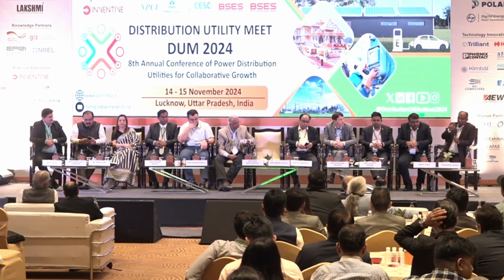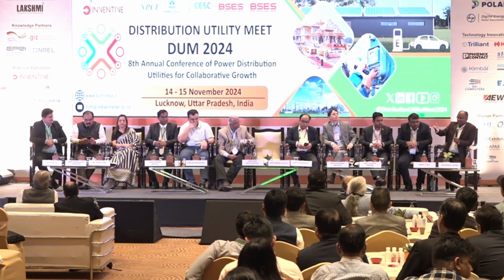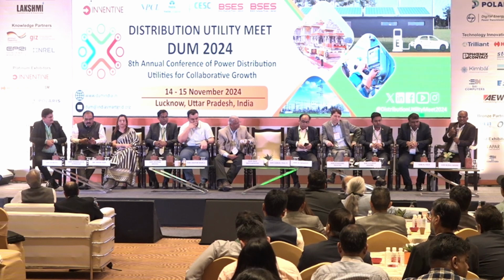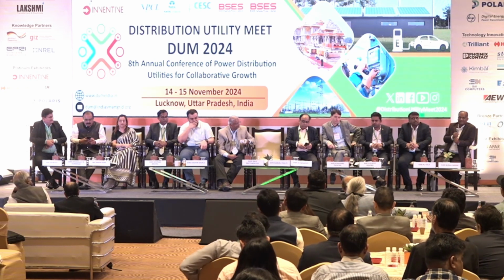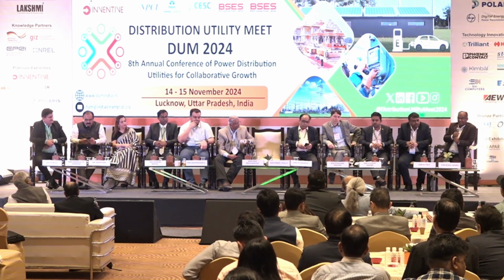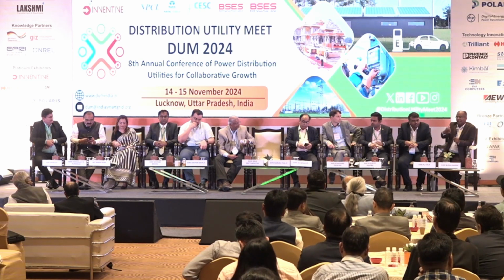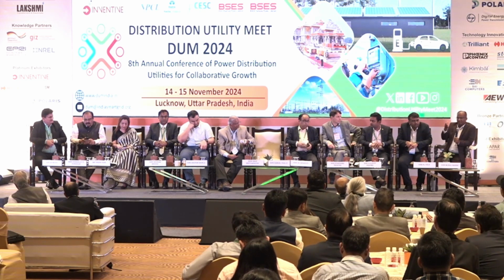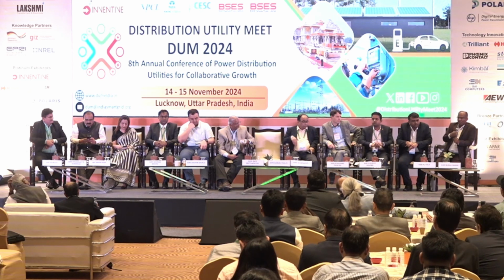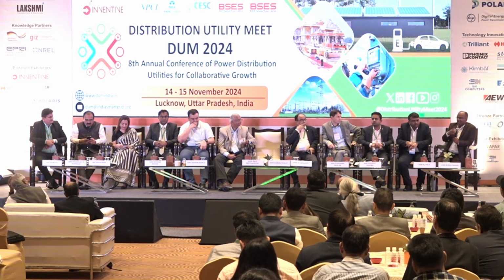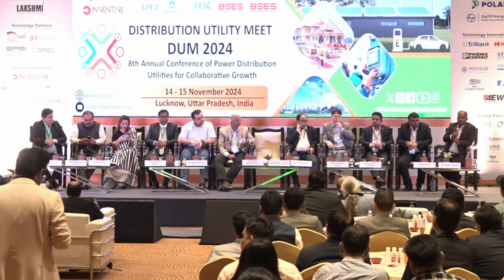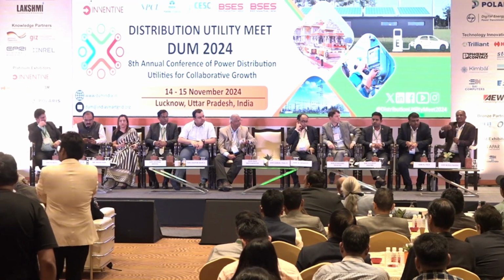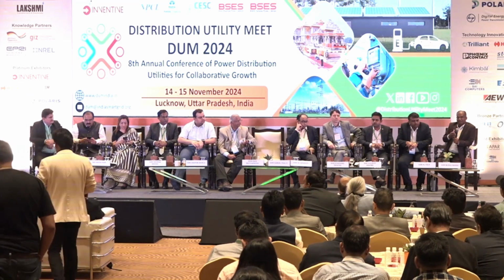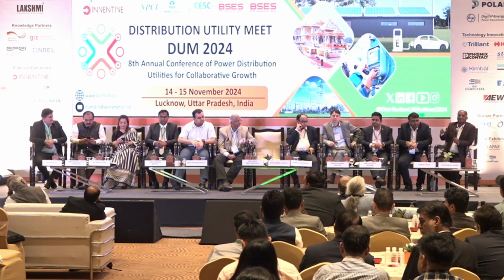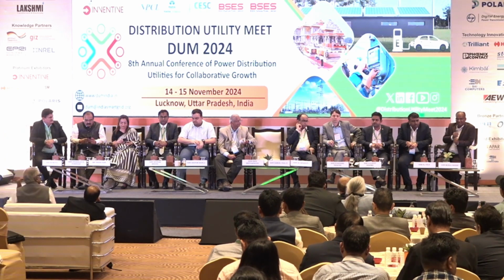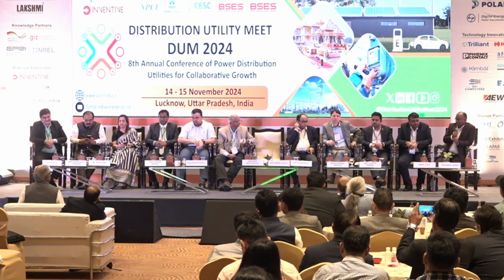I also want to mention where we're heading—even this isn't fully done within the US, we're actually trying grid forming inverters. That's where parts of the grid can be islanded when a big event happens, like a cyclone hitting the system, but islands can be made with these grid forming inverters. I think that's the next generation, but again we need to make sure we take care of safety and protection concerns of the system as we do that.